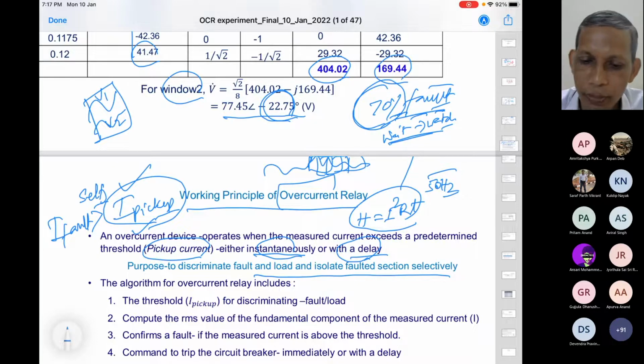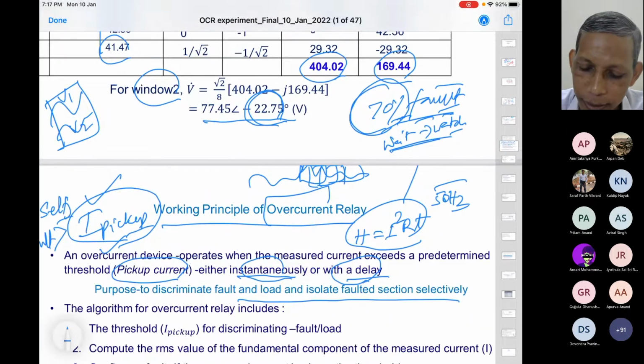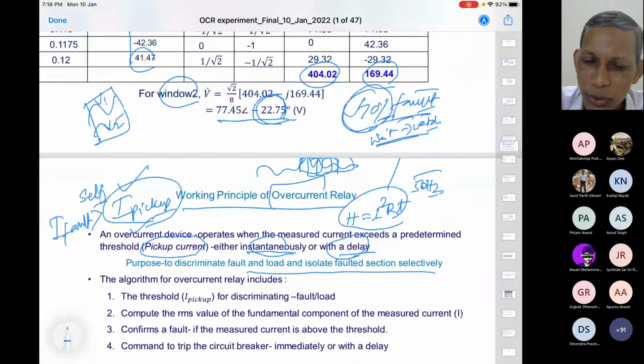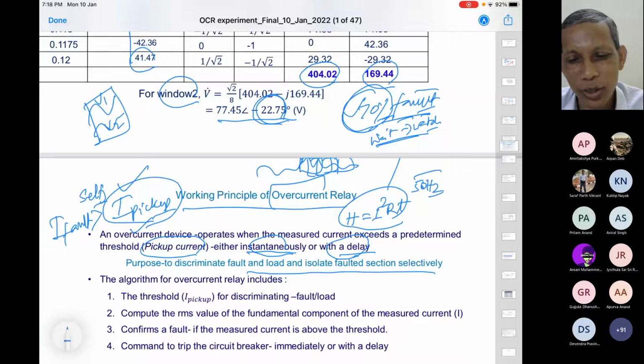If the fault persists for a period of time, the critical clearing time comes into the picture, and there we require speed of operation. What is being done, for your information, is that we can now put more intelligence into the relay. We call it the reclosing phenomenon. Any fault, transient, transitory, permanent, whatever, trip it, and then switch on again after some time. Many times you must have seen that the system is restored after some time. Agree?